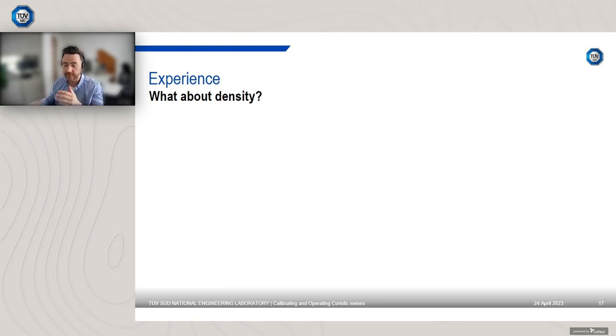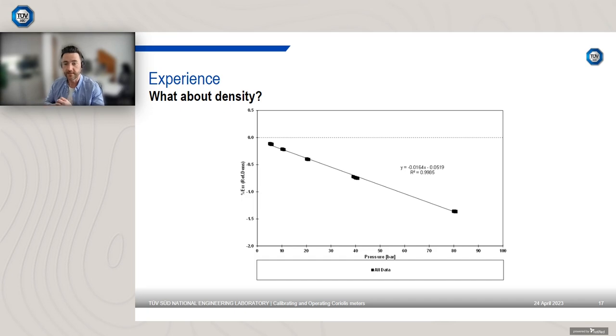So a question we're often asked: Coriolis meters can measure mass flow, but they also measure density. Is there a pressure effect for density? And the answer is yes. So again, I have a different meter type here. I've operated up to 80 bar again. Again, I like to pick similar pressure points to use, just because they're multiples of one another. So 5, 10, 20, 40 and 80 gives you a nice linear effect.